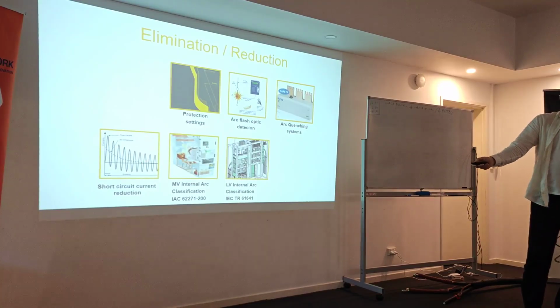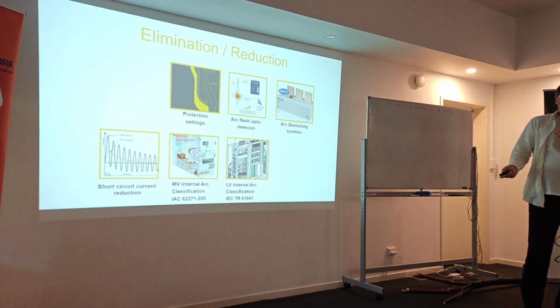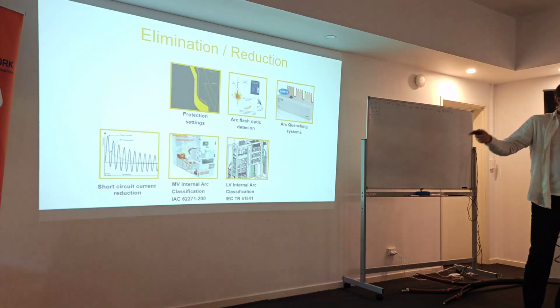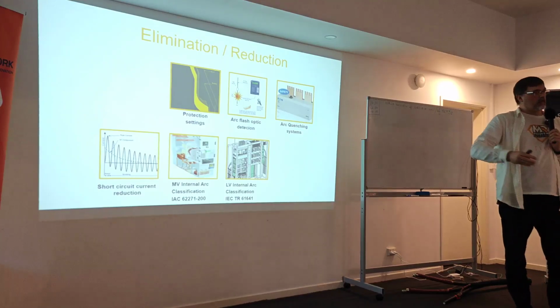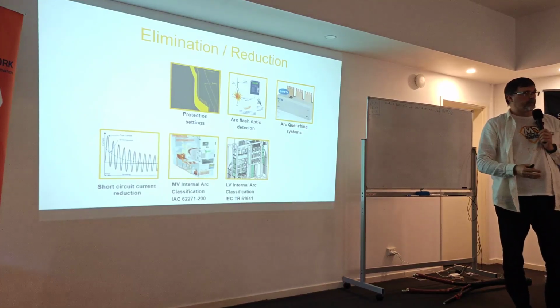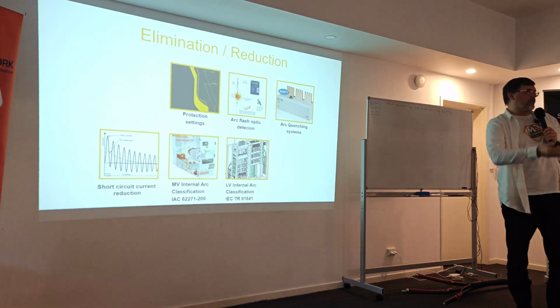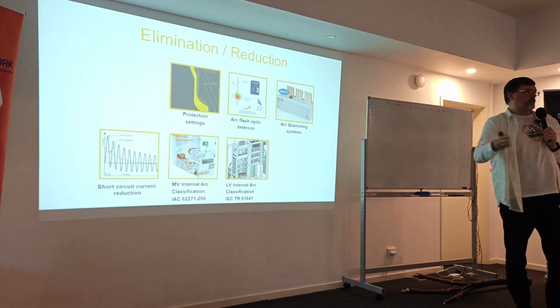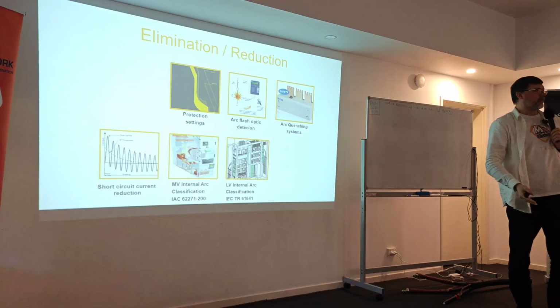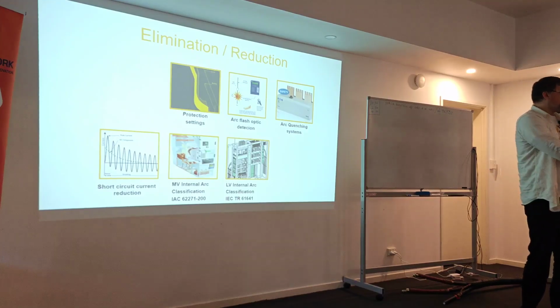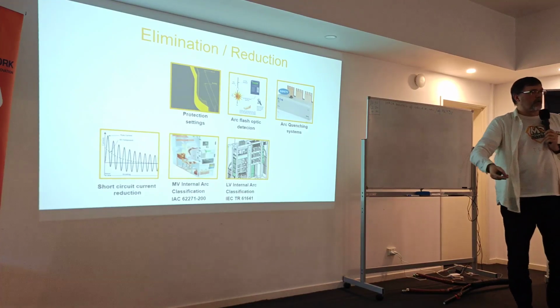Short circuit current reduction on big networks, when you have current limiting reactors, does not always mean the lowest short circuit, and does not always mean that you have less of a problem. Sometimes, because short circuit has an influence on the protection time, you can go too low and then your protection will not pick up. That's the problem with PV, that's the problem with the inverters, yeah? With the tripping.